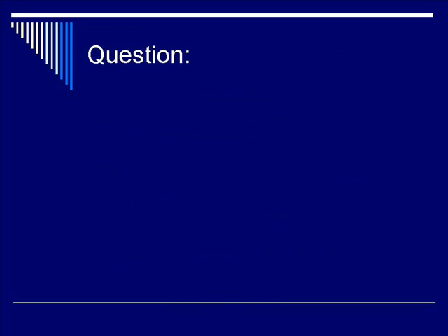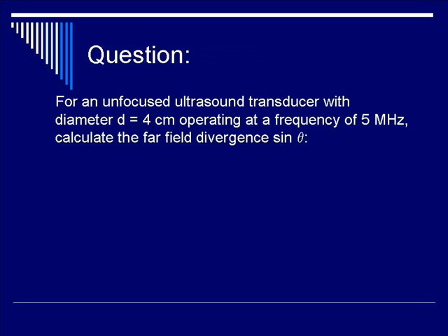Let's do a question. For an unfocused ultrasound transducer with diameter D equals 4 centimeters operating at a frequency of 5 megahertz, let's calculate the far field divergence, sine theta. Utilizing the equation sine theta equals 1.2 lambda over D, is the answer A: 0.009? B: 155.8? C: 0.09? Or D: 0.15? Let's pause the video to work out your response.